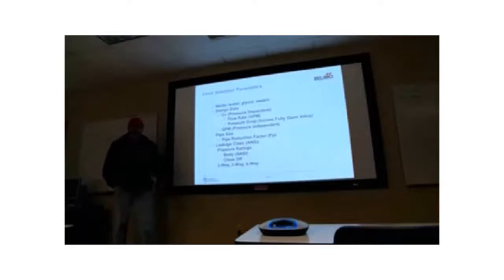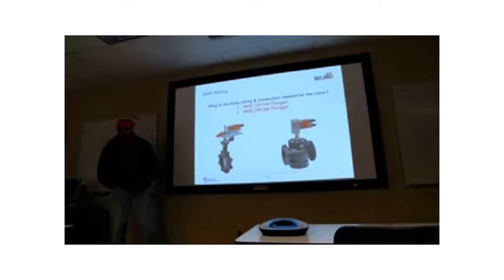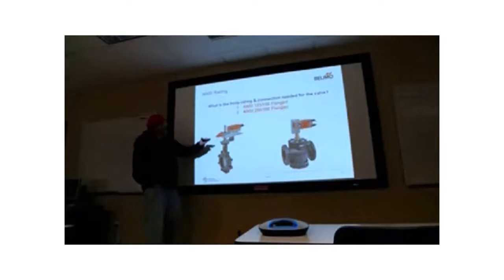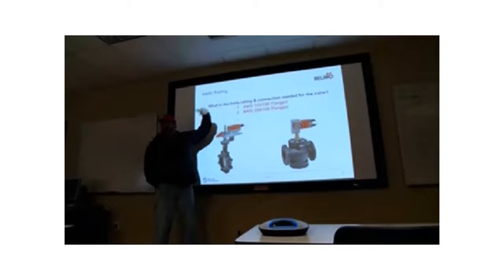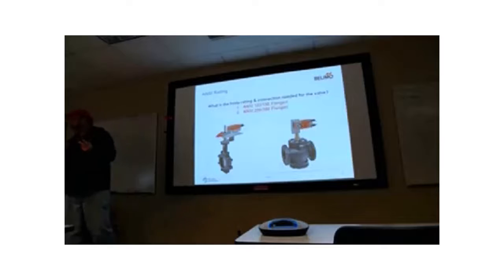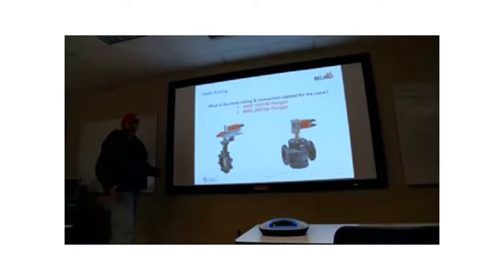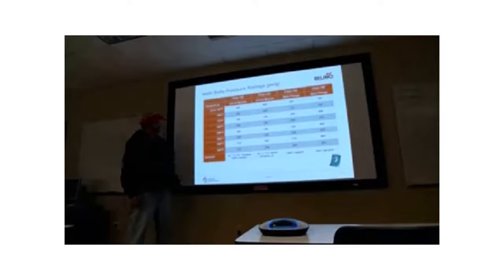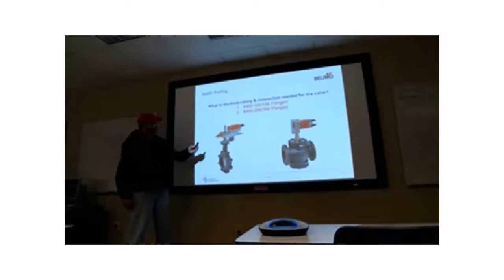We have what we call body ratings or pressure ratings for valves, and this is the general thing for HVAC. We have what we call ANSI. ANSI is just the American National Standards Institute. We have a class, ANSI 125 and 150. This has to do with cast iron, right? And 250 and 300 actually have to do with malleable iron or ductile iron type fittings and valves and things like that. And then we have non-rated ANSI.